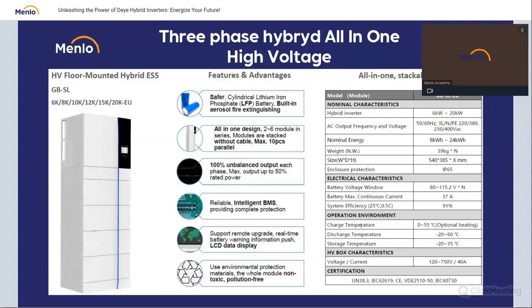So it's the best result on the market. No one else gives you that; only three brands give phase unbalance, and no one gives such a big ratio of unbalancing. Okay, so at the end, coming back to backup limitation with a three-phase inverter. With single phase, it's simple. You don't have a limitation per phase. You have only the limitation of the inverter. It's for small systems. So the backup limitation is the inverter power, that's obvious. The power of the inverter which you choose is the inverter power limitation.